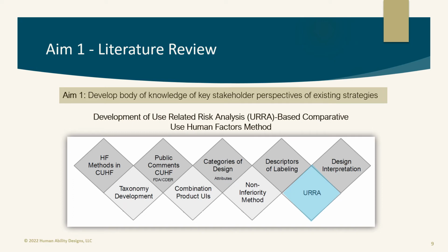Also in aim 1, we've conducted an extensive literature review with one part being focused on the use-related risk analysis, or URRA. A little history for you. The URRA was first mentioned in the 2016 Draft Guidance on related clinical study considerations in combination product design and development.